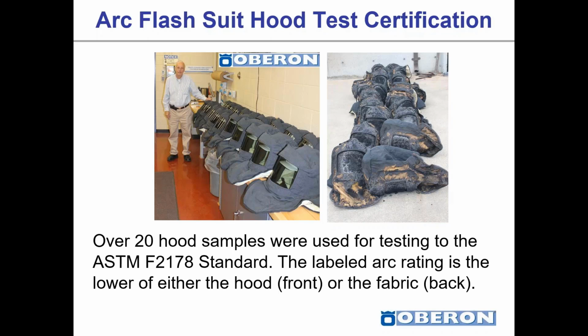In the case of Oberon hoods, just for example, the front of the hood with that clear gray lens provides significantly more protection compared to the fabric itself. So we rate the hoods as the fabric rating, because if the worker is facing away from the arc flash, the weakest point of the hood would be the fabric itself.